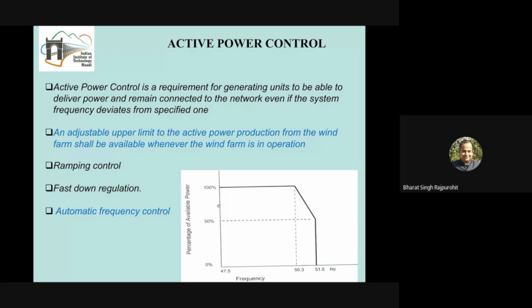Some of the philosophy may be used for participation in the automatic frequency control. Now you will be able to see that a curve is also given here, which says that once the frequency goes above 50.3, the power should be reduced at a certain rate, and if the system frequency is beyond 51.5, generation should be stopped completely, with 0% power output from the wind turbine. So this curve should be followed by the wind turbine by appropriate technology.